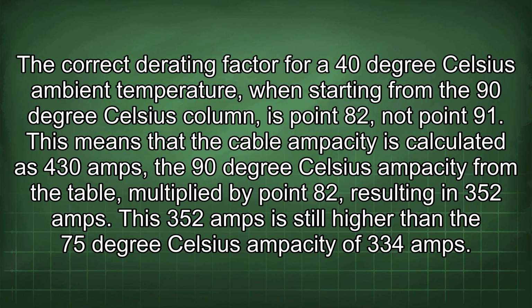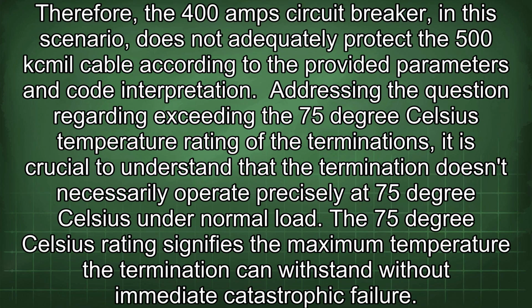This 352 amps is still higher than the 75 degrees Celsius ampacity of 334 amps. Therefore, the 400 amp circuit breaker, in this scenario, does not adequately protect the 500 kcmil cable according to the provided parameters and code interpretation.